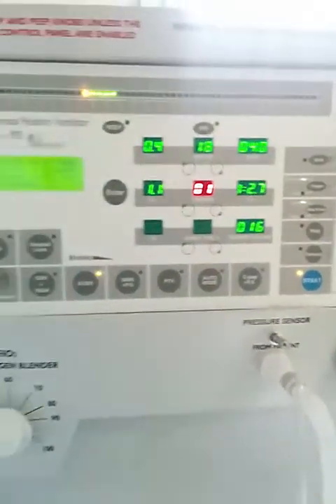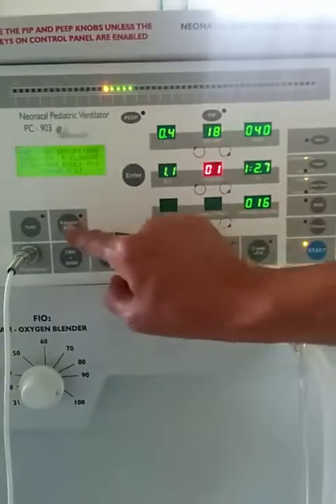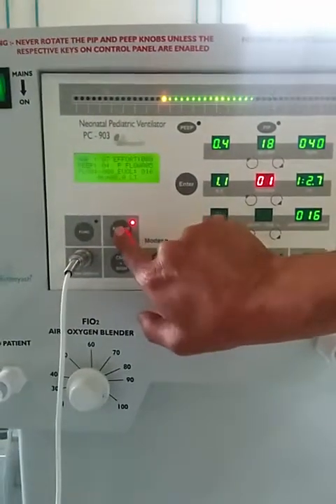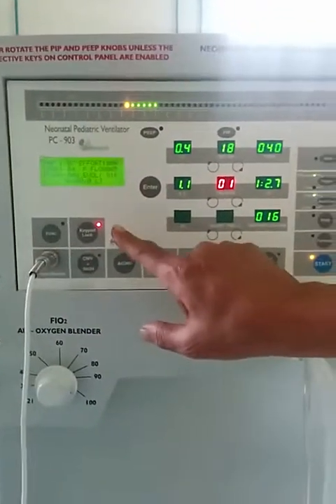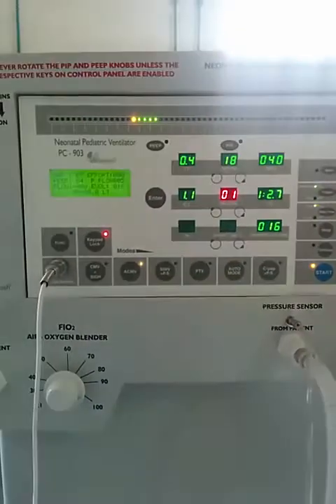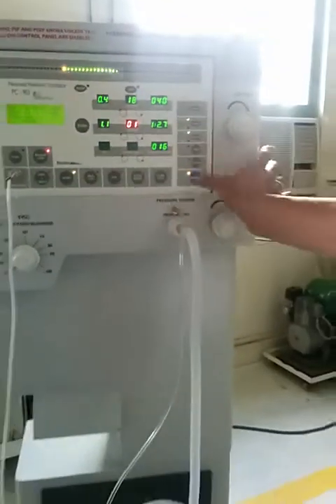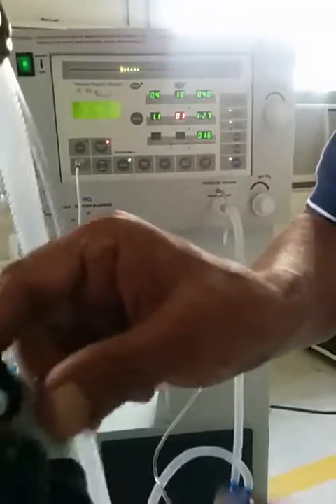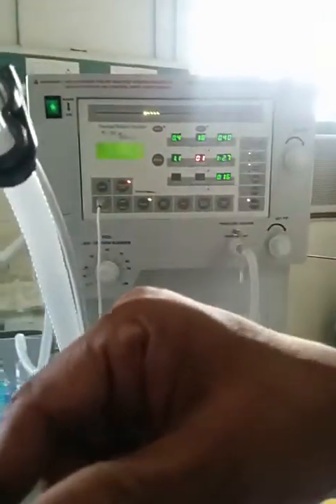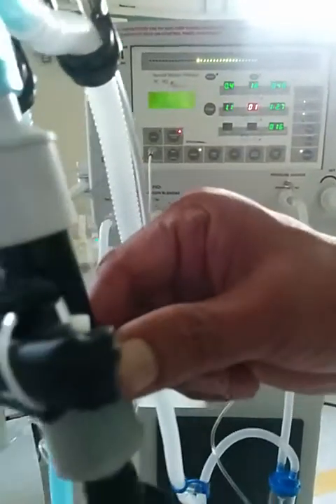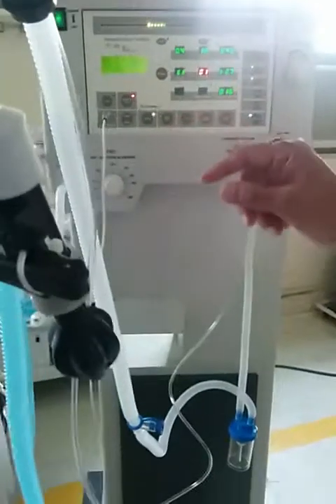Now all your parameters are set. Then press this keypad lock, so now nobody can change your settings. We are now out of the settings. After which, stop the machine, remove the test lung, put in an endotracheal tube and connect the patient to that. That's as simple as that.